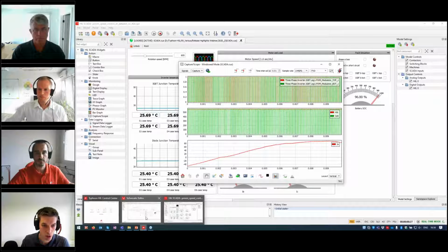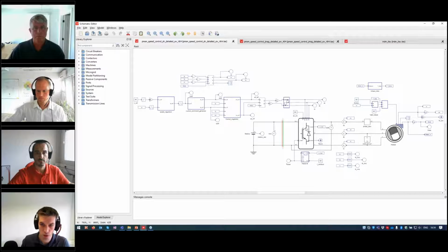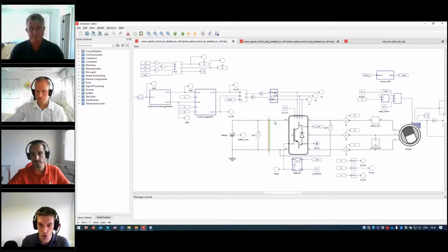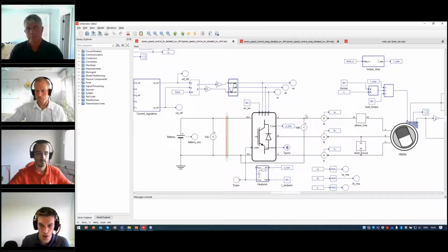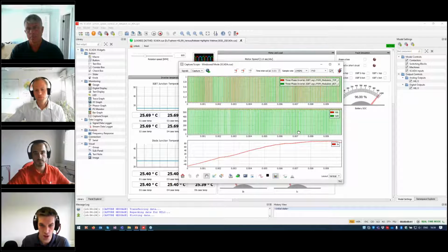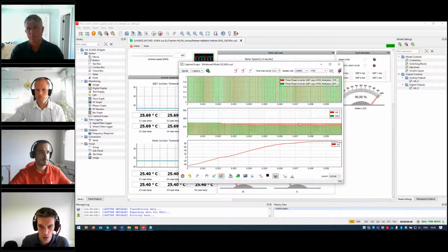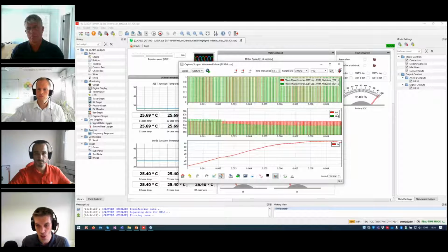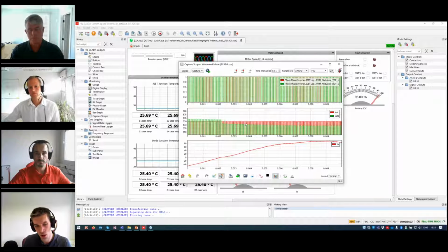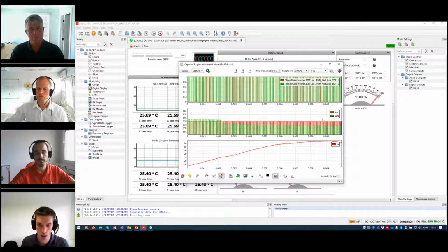So what I'm showing here is the gating signals for the leg in phase A. I'm showing the DC link voltage, the A phase to negative DC link voltage, and phase A current. So we can see that when the current is positive, the phase voltage to negative DC link is actually not equal to the DC link voltage, but it's somewhat less due to the forward voltage drop. And we can clearly see that it's not only a fixed voltage value, but it also depends on the current. So the higher the current, the larger the voltage drop.